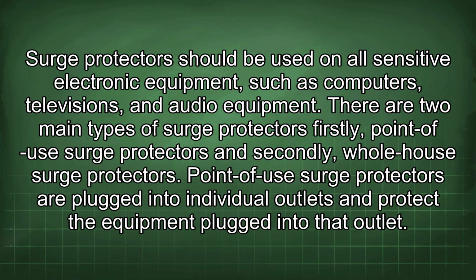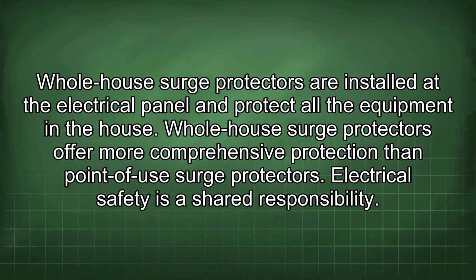There are two main types of surge protectors: firstly, point-of-use surge protectors, and secondly, whole-house surge protectors. Point-of-view surge protectors are plugged into individual outlets and protect the equipment plugged into that outlet. Whole-house surge protectors are installed at the electrical panel and protect all the equipment in the house. Whole-house surge protectors offer more comprehensive protection than point-of-use surge protectors.